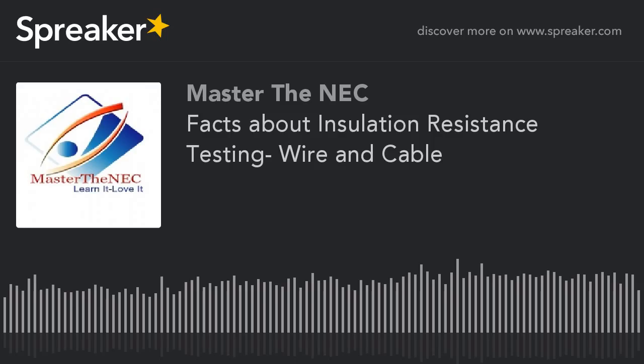I'm just trying to give you a little down and dirty on those types of things, because for years as an electrician, I've read manual after manual that says check A to B, B to C, A to C, each individual conductor to ground, the equipment ground, and look for those readings. And the reality is no reading is near the same. You might have the same product, the same cable, the same individual conductor produced on the same day. It's the same reel. You take the same lengths, you put them in raceways, and you're going to get different results.